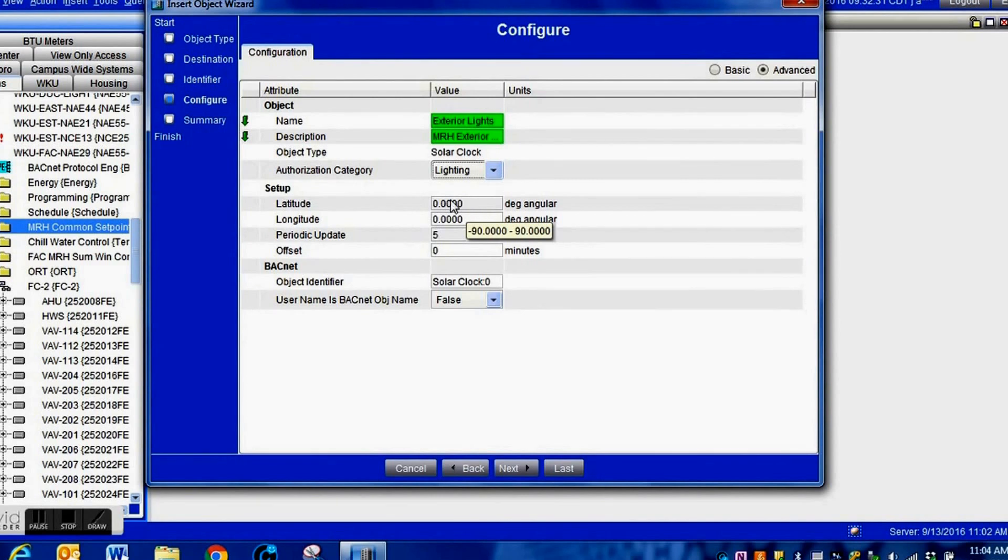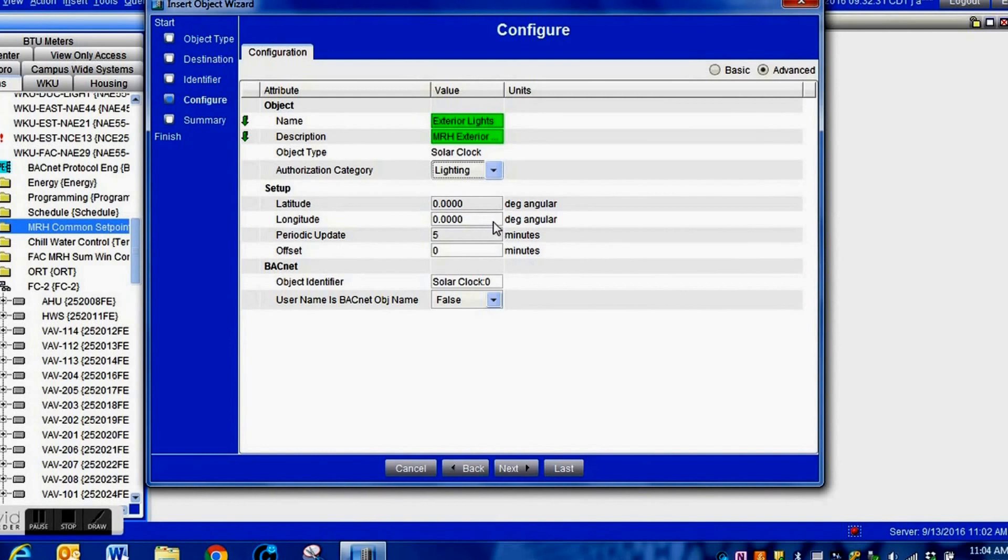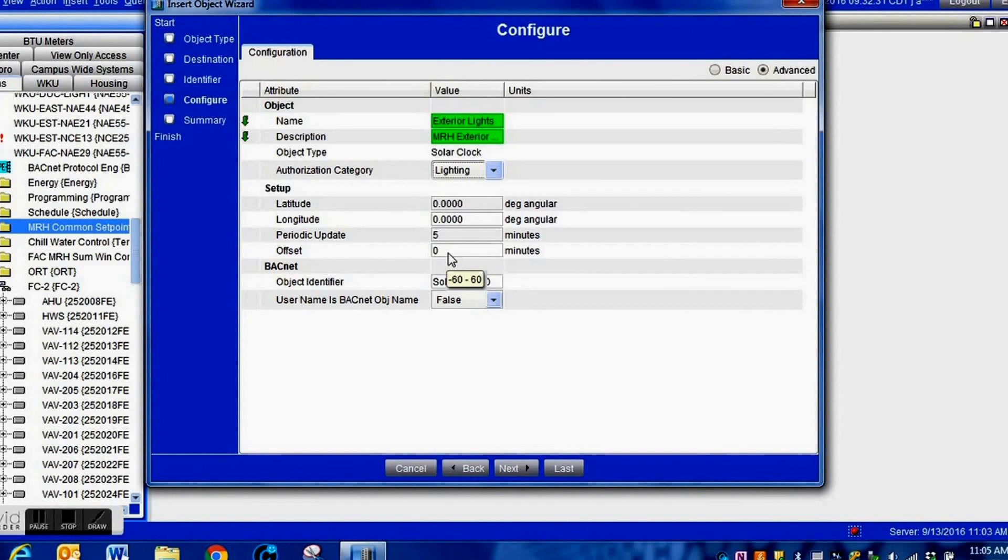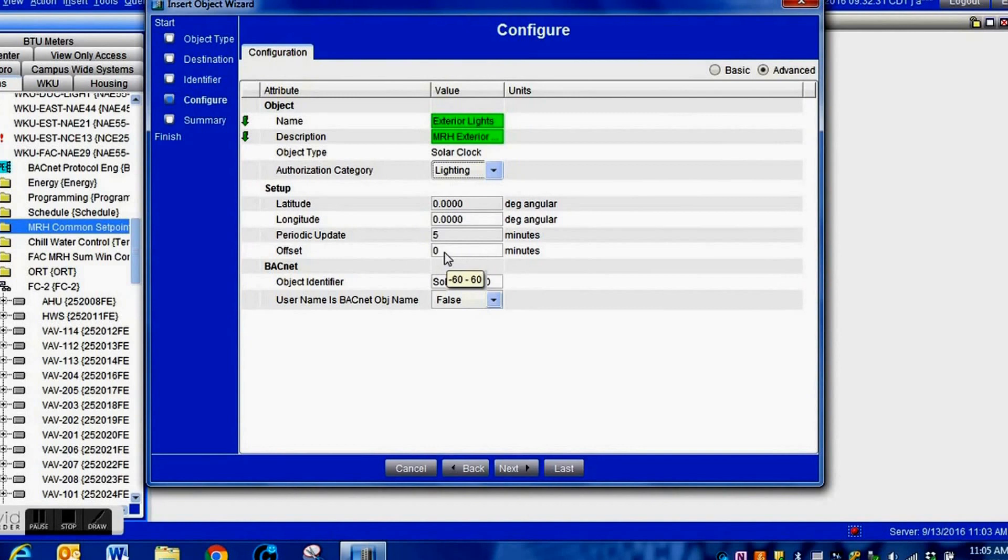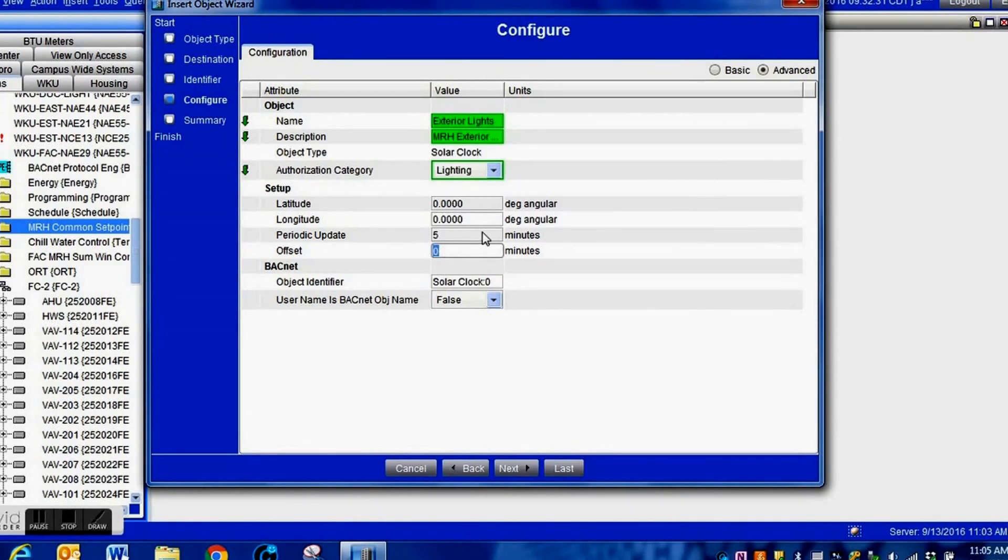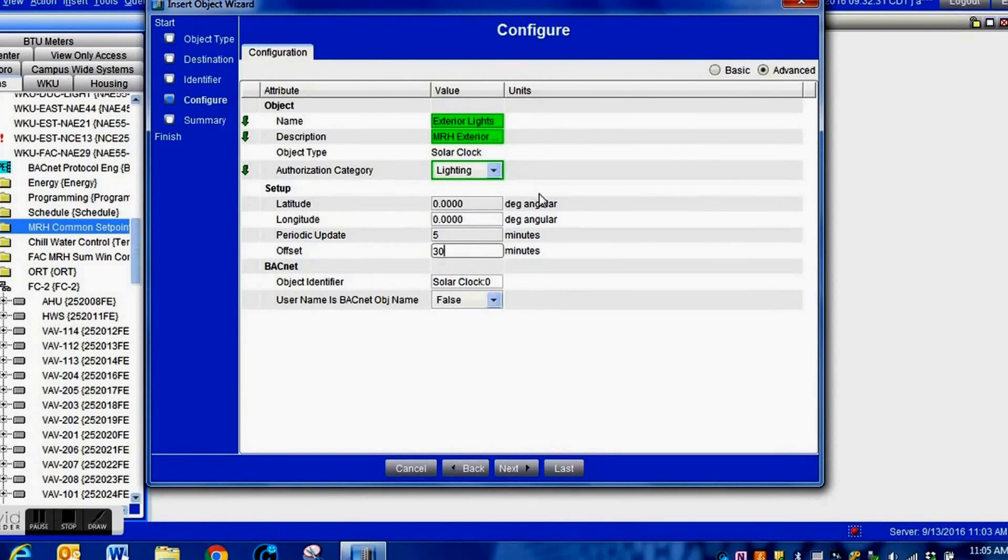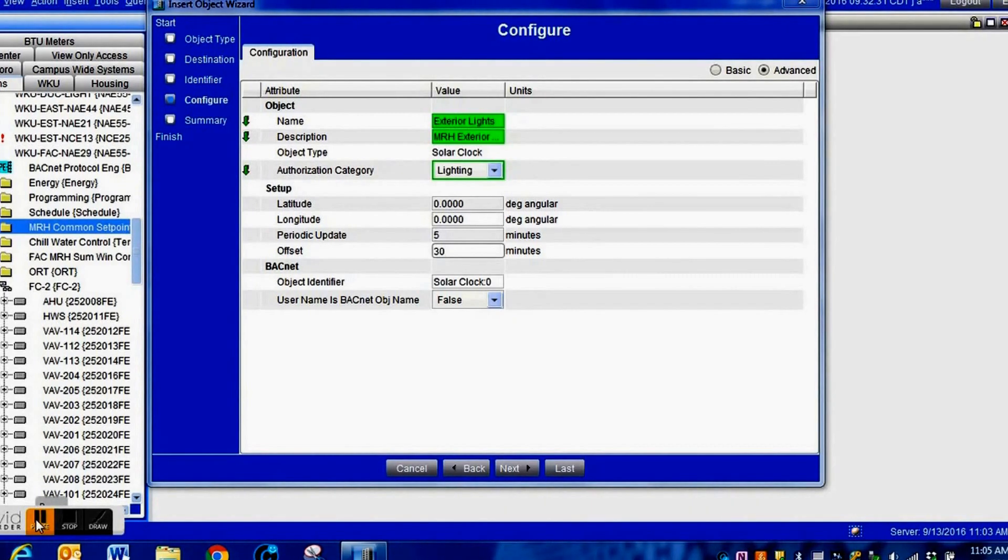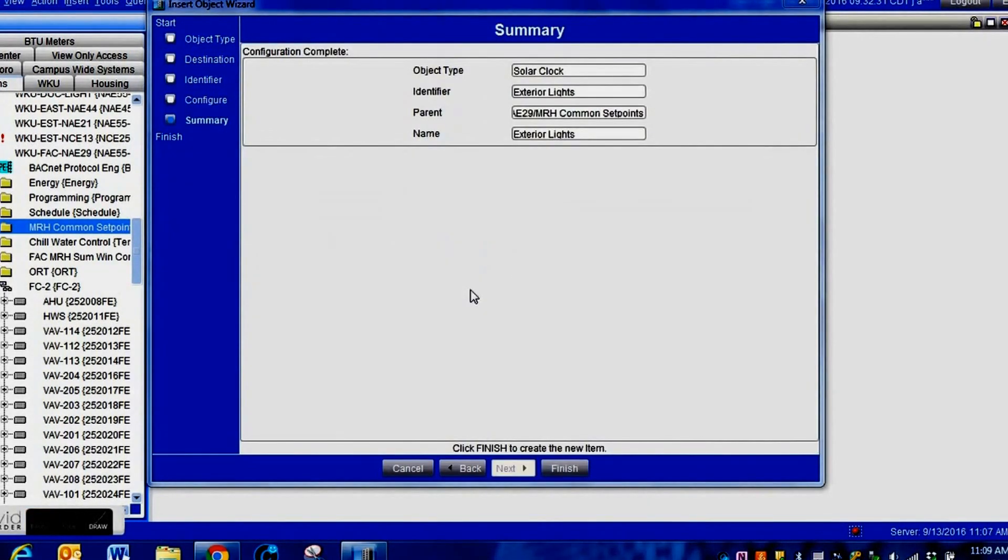You need to be sure that you enter it exactly. If you are off just by a little bit, this solar clock will not function correctly for your area. You can enter your offset here if you want to delay the switching from on to off. We're going to put a 30 minute delay in here for now, and it is possible to change that later. I can't stress the importance of making sure you get the latitude and longitude correct.